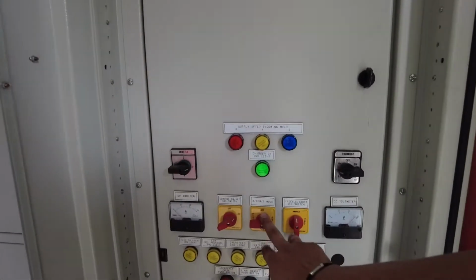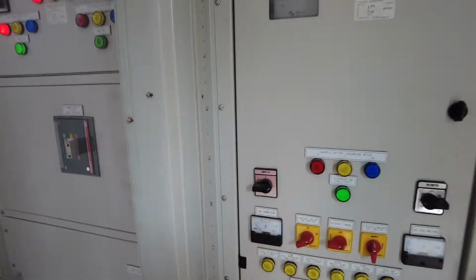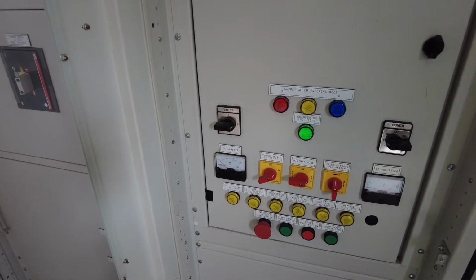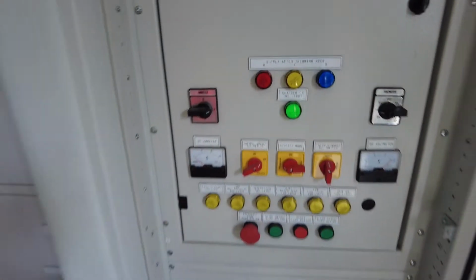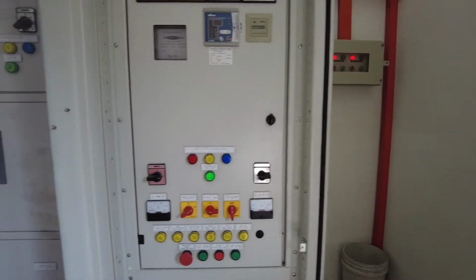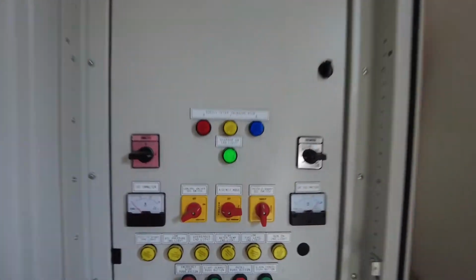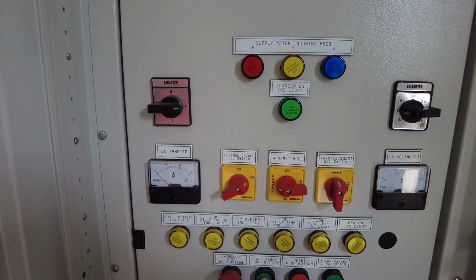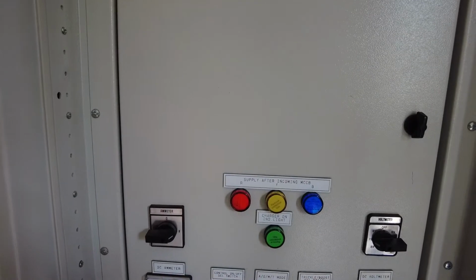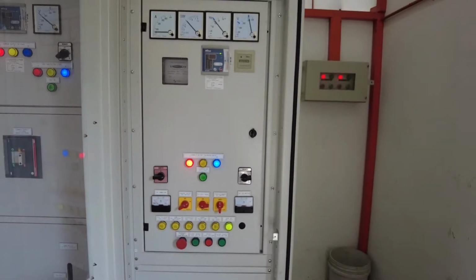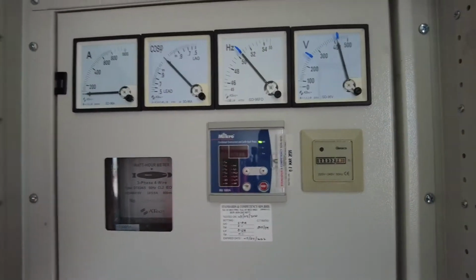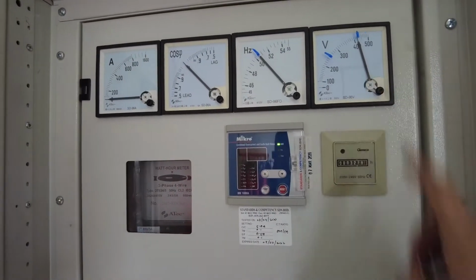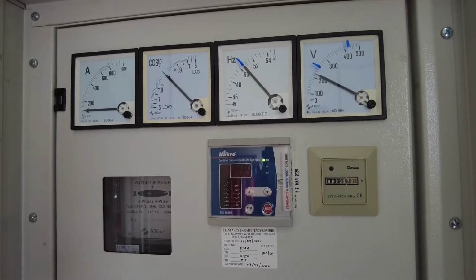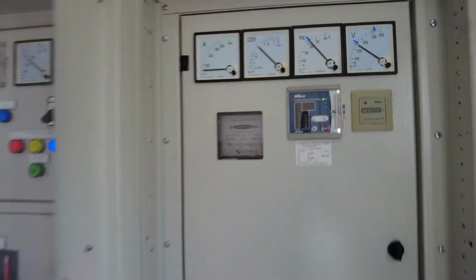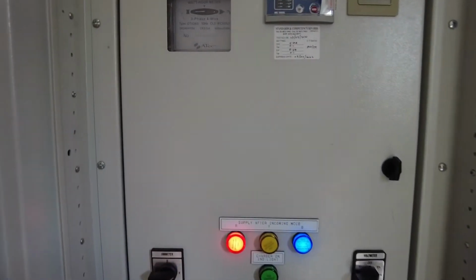Okay. Just then we test from the controller module using test mode. Okay, now we are going to test using manual mode first. Manual mode, we see whether can run manual or not from here. Then only we jump there. 3 kali test. Sudah jalan kan? Okay. Now it's running. Voltage is okay. We check the voltage. 415 okay. Single phase okay. Frequency okay. Okay, there's supply. Okay, then we put back auto.